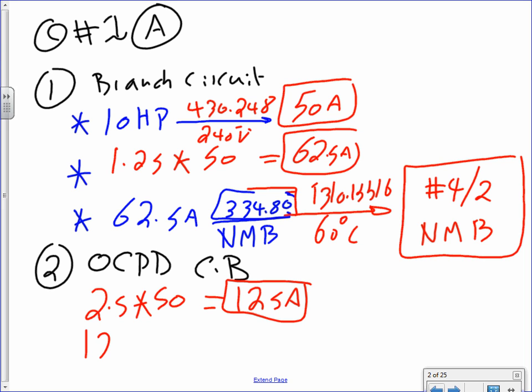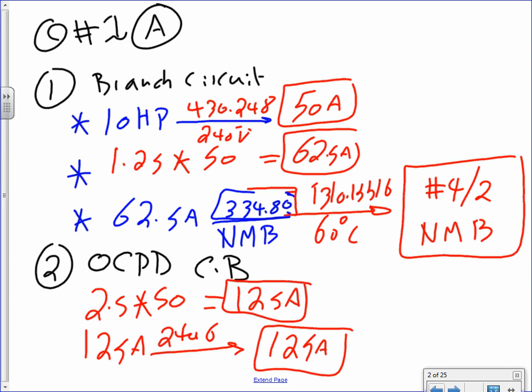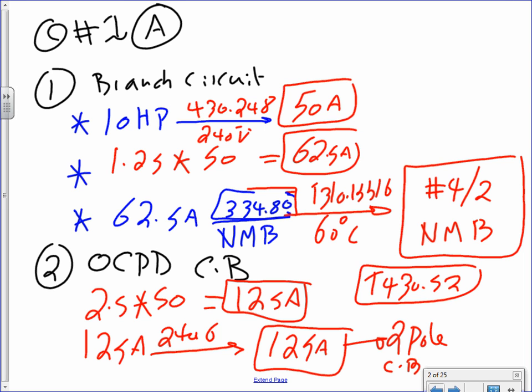You take 125 amp, take this one to 240.6, and that will get you a 125 amp size. It's already a size. It will be a 2-pole circuit breaker. This is a 2-pole circuit breaker, and this is coming from Table 430.52. You remember that? That's where the 2.5 comes from. Any comments, any questions?